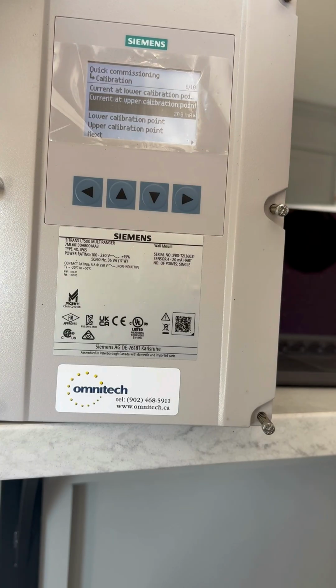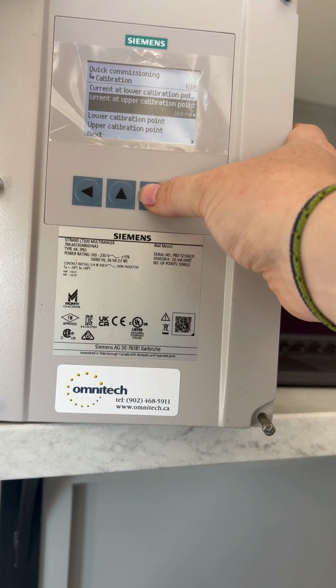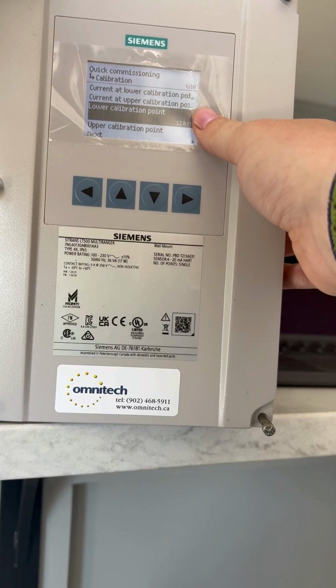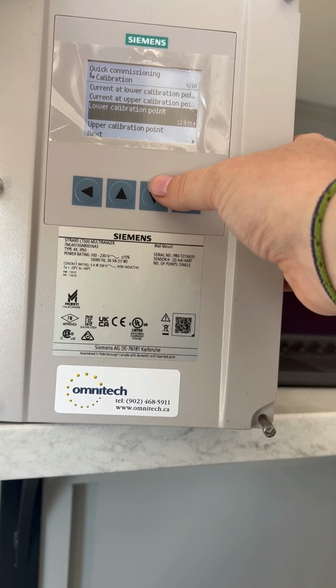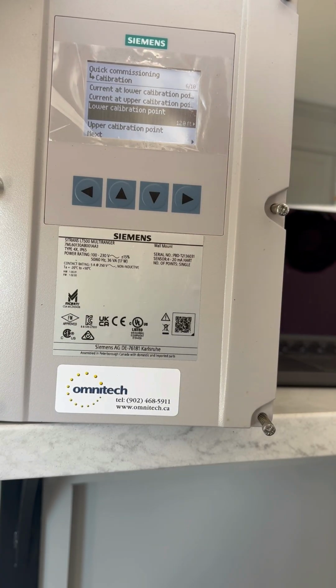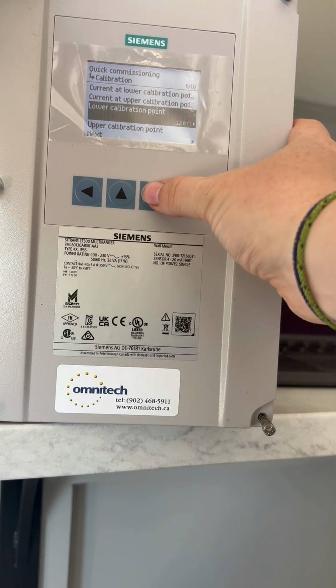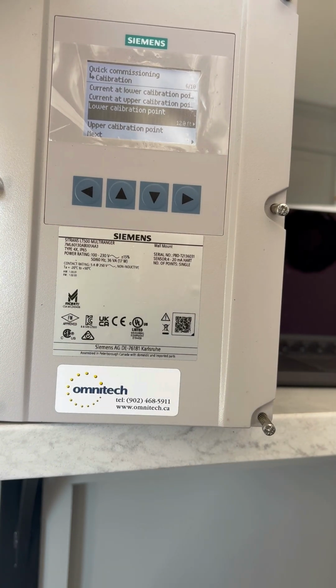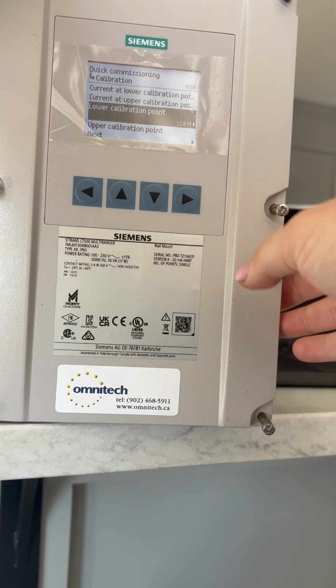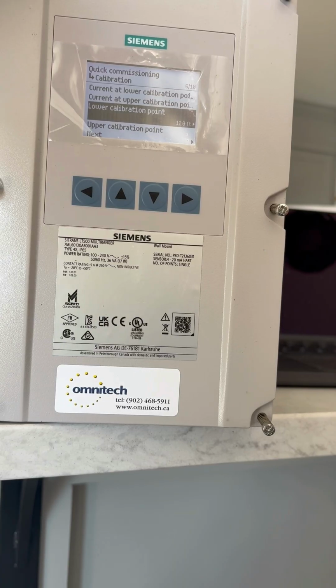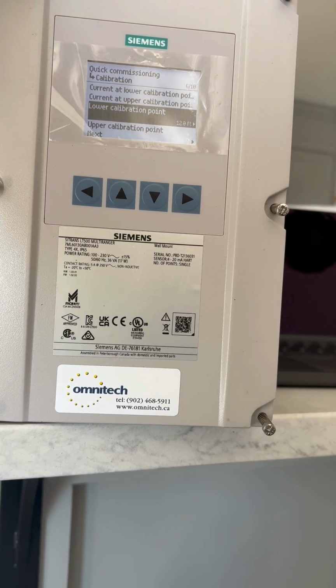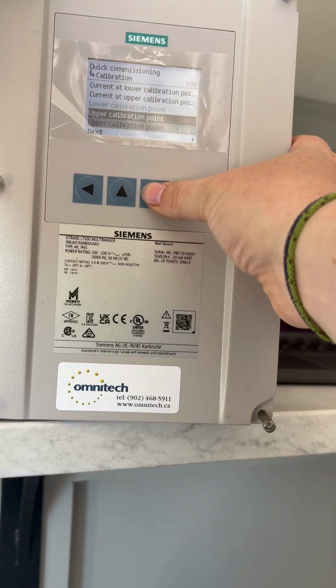That could be changed. There's sometimes applications where we need to change that, but we don't need to in this case. So as you can see, my lower calibration point is 12 feet. Again, that's from the top down to the very bottom. How deep are we going? So that's when you install the sensor. If it ends up being something different, we don't have to change that. We can if we want to match it, but we can also keep that at 0 to 12, because if it does actually rise any higher, or if something happens with the application, it would show that.